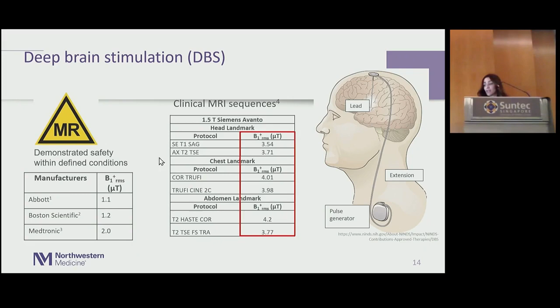So the first thing that I do, again, I'm an electrical engineer and a nerd in terms of I love simulations and I look at electric fields and magnetic fields, and the only way that you can see them is to simulate them. We created a model of a patient with a deep brain stimulation lead, and we just looked at the amount of SAR, which is the specific absorption rate of the energy at the tip. And we saw a substantial 20-fold reduction in SAR in an open bore vertical scanner compared to a horizontal.